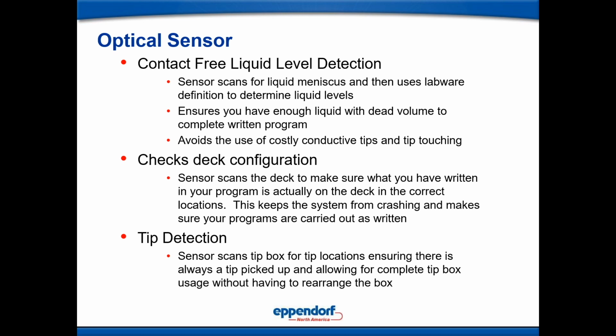The second bullet point there checks the deck configuration. This is so important because if you put things in the wrong place, and humans always do, sooner or later you're going to do it. Most machines will just go there thinking that there's something, and if that item is higher than the item that's supposed to be there, it will crash into that item. It could cause steps to be lost on the Z-axis. It could cause damage to the Z console. It will certainly need to be recalibrated if you crash the machine.